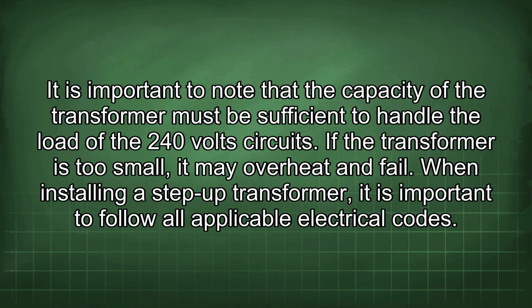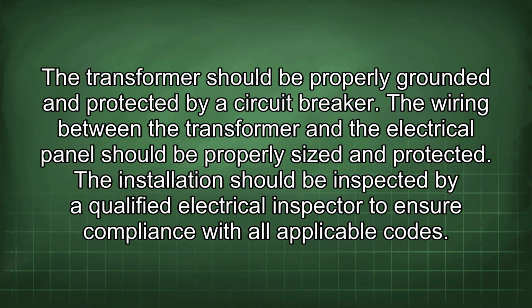It is important to note that the capacity of the transformer must be sufficient to handle the load of the 240 volt circuits. If the transformer is too small, it may overheat and fail. When installing a step-up transformer, it is important to follow all applicable electrical codes. The transformer should be properly grounded and protected by a circuit breaker. The wiring between the transformer and the electrical panel should be properly sized and protected. The installation should be inspected by a qualified electrical inspector to ensure compliance with all applicable codes.